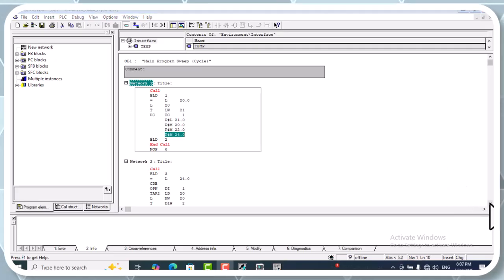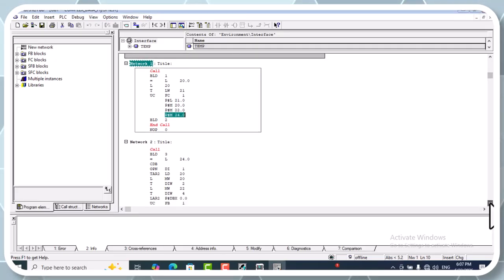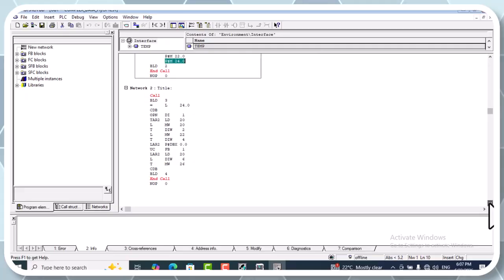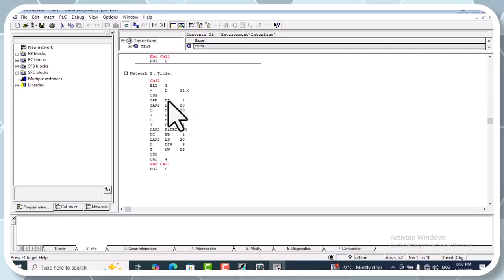So my friends, now let's look at how the Simatic Manager sends parameters to the FB block, and you can see the difference between FC and FB blocks. Here, firstly we have our DB block number, and this command writes the number of our DB block to a special register, which we call the DI register.